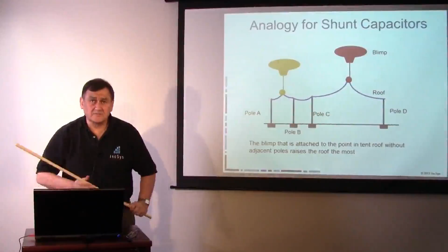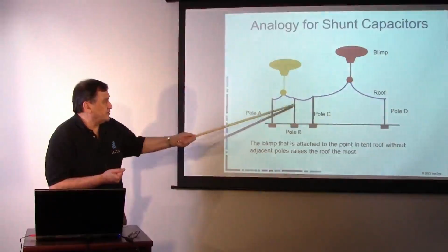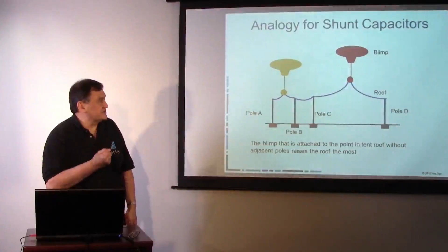Now, the analogy we have for shunt capacitors is they are like a blimp that lifts the voltage. This shows that two capacitors, or two blimps the same size, when they are lifting a part of the roof that is close to the poles, give very little voltage rise. But it's really important to understand that you may have a low voltage situation in a very weak part of your system. You apply that shunt capacitor, you could go from 92% to 120% voltage, just like that. So it's really important to understand the relative strength of the buses throughout your system.